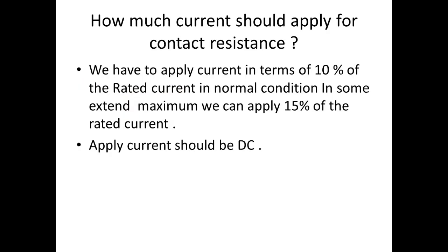Finally, how much current should we apply for contact resistance testing? We have to apply current in terms of 10 percentage of rated current or nominal current value of the conductor. In some cases, the maximum we can apply is only 15 percentage of the rated current, using DC current for this test.